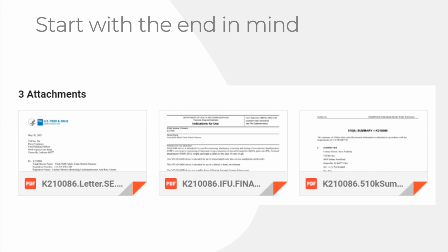You are not required to do a 510K summary. It is always revised by the FDA. They always ask us to make changes on the 510K summary. If you don't want to deal with all those changes, you can do a 510K statement. Whether it's an eCopy or an eSTAR, you can still do a 510K statement.